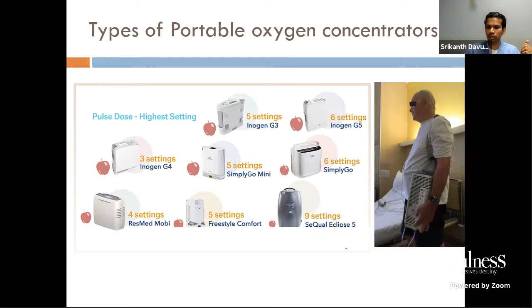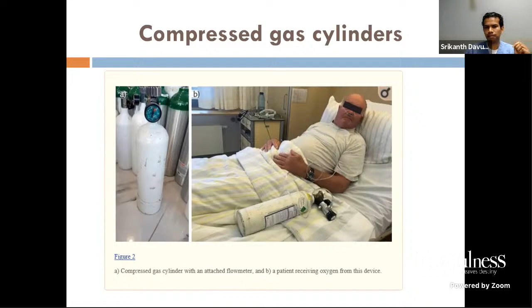The next is the compressed gas cylinder. It's nothing but a metal cylinder in which you store the oxygen, and usually you have a regulator and a barometer on the top of it. The regulator is like a tap. The more you open it, the more flow you get. So this is a continuous flow. The barometer will tell you how much pressure is in there, which describes how much oxygen is in there.